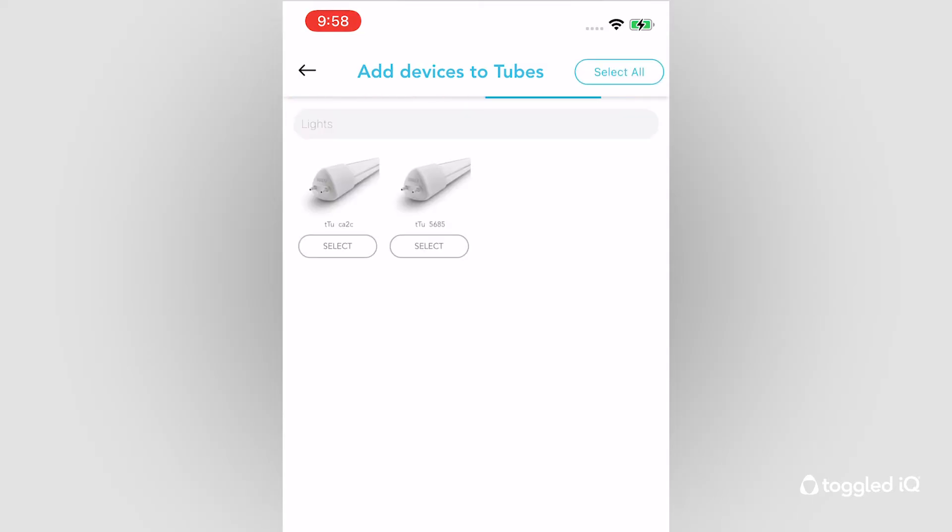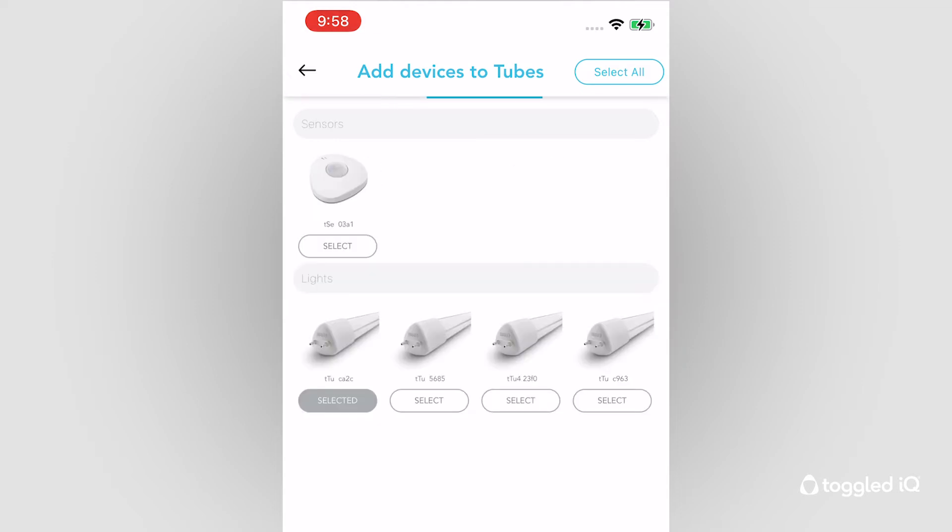For instance, concrete walls and floors may reduce range, so they should be accounted for. Commissioning devices on other floors or generally out of sight from you or your mobile device should be avoided. When provided power, Toggled iQ devices will announce their presence via Bluetooth to assist in the commissioning process. To streamline the process and prevent overwhelming your new network, we recommend commissioning no more than 20 new devices at a time.